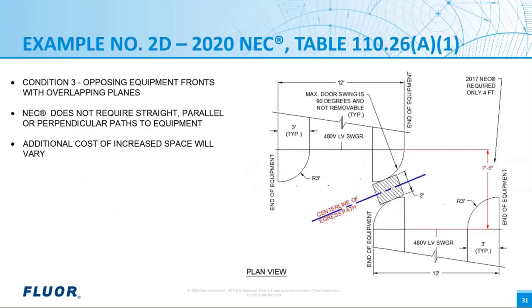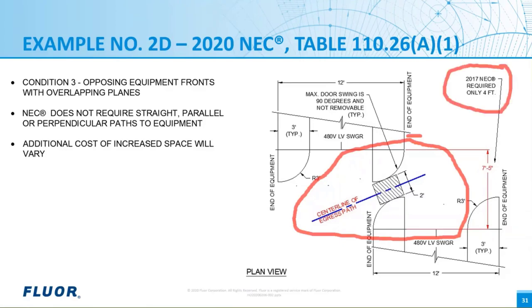All right, a scenario like this wasn't really a concern before the 2020 NEC because we provided spacing between the front of the two equipment based on the applicable condition in Table 110.26(A)(1). Let's say we have a scenario like this now. There is nothing in the NEC that says the entrance and egress path has to be in a straight line. We just need to have a minimum of 24 inches to be able to get in and out of the workspace. So then the question is, is this acceptable? Does this meet the intent of the new revision of the NEC?